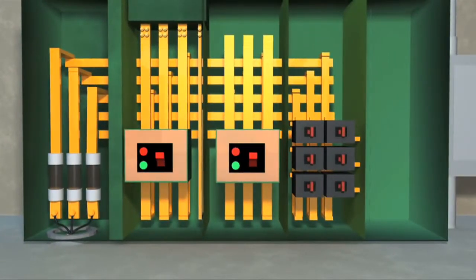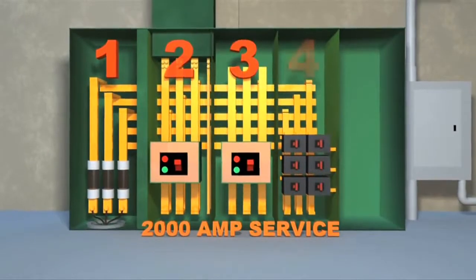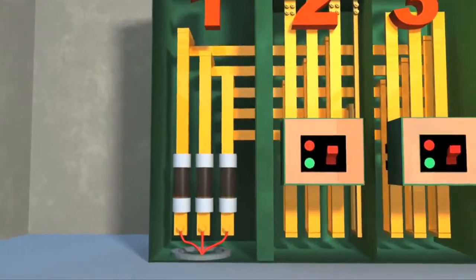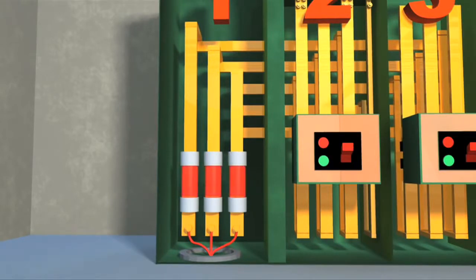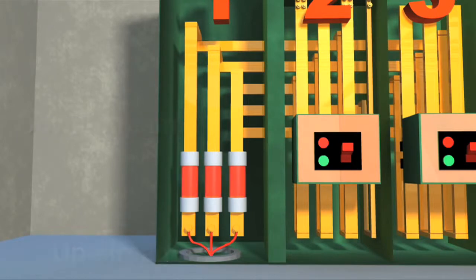Here in our example, we have switchgear that is rated at 2000 amps. It consists of five sections connected together. As you can see, section one contains the incoming voltage connected to the main fuses. These main fuses protect the downstream electrical equipment within the switchgear from exceeding 2000 amps. In the event that more than 2000 amps are drawn, these fuses will open and disconnect voltage.